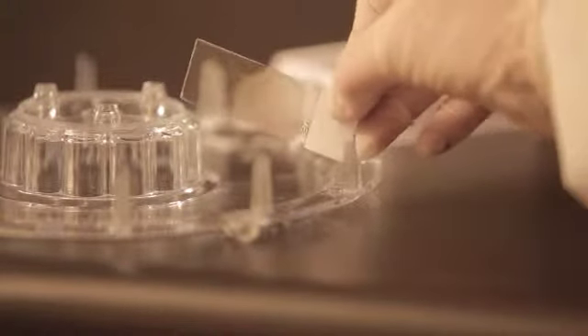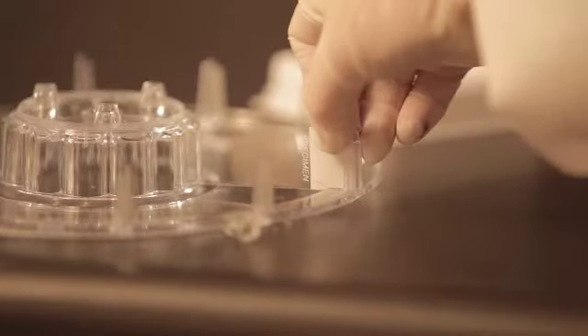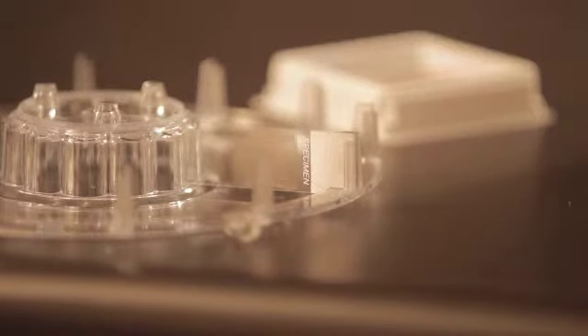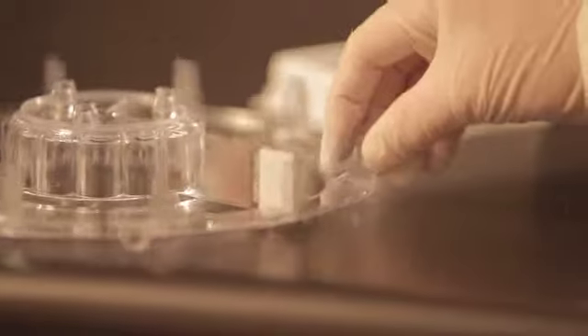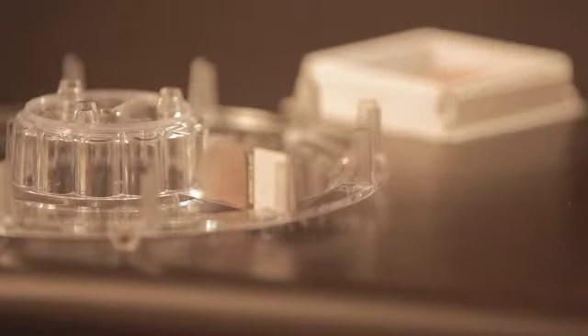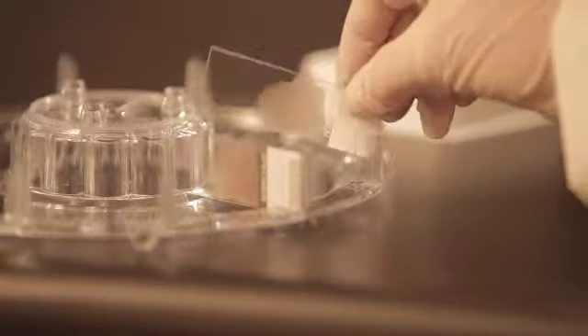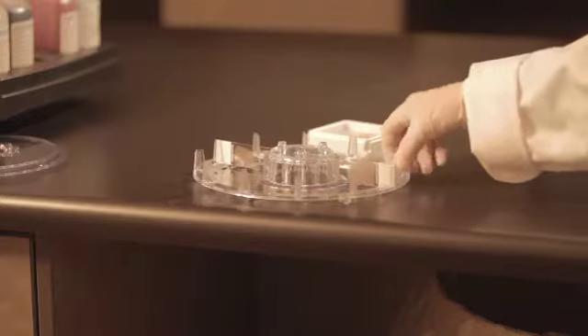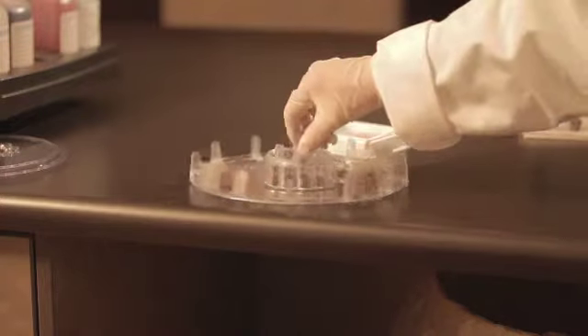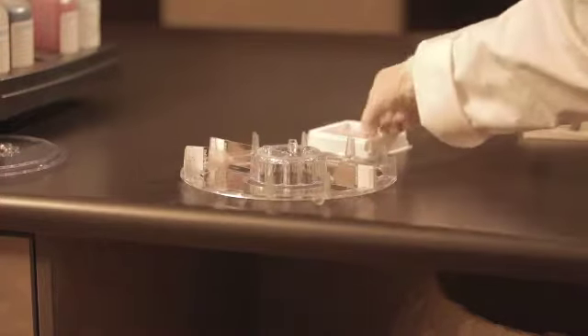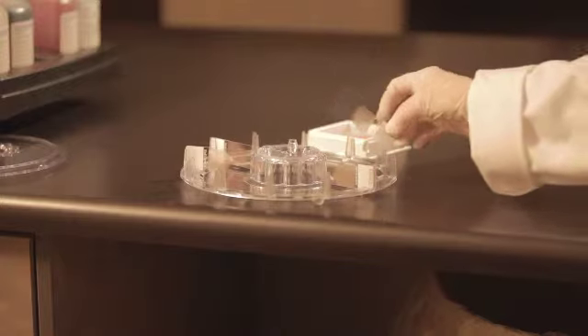Step 6, loading the carousel, is quite simple. The carousel is numbered to help load the slides in the proper position in the carousel. Loading the slides in the proper position is key. Start with the number 1 position on the right side. Load the slide with the specimen facing forward. Rotate the carousel 180 degrees and load the next slide in the number 2 position. And rotate again to load number 3 and so on. The numbered slide position in the carousel is important so that the carousel is balanced.